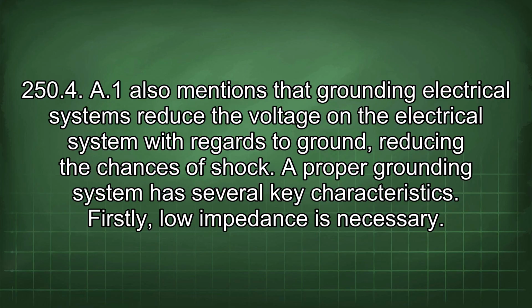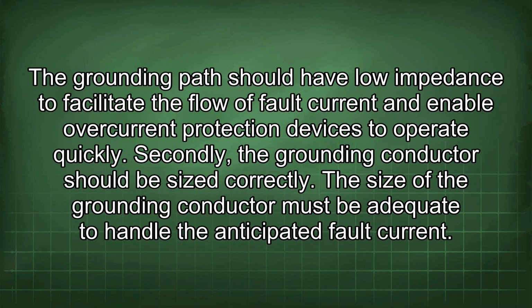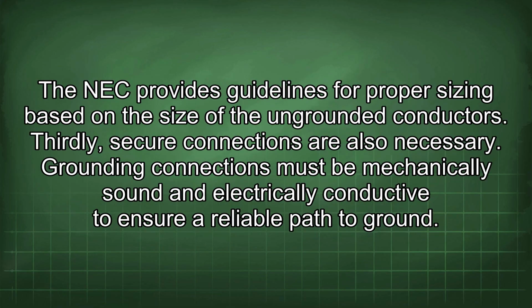Firstly, low impedance is necessary. The grounding path should have low impedance to facilitate the flow of fault current and enable overcurrent protection devices to operate quickly. Secondly, the grounding conductor should be sized correctly. The size of the grounding conductor must be adequate to handle the anticipated fault current. The NEC provides guidelines for proper sizing based on the size of the ungrounded conductors.